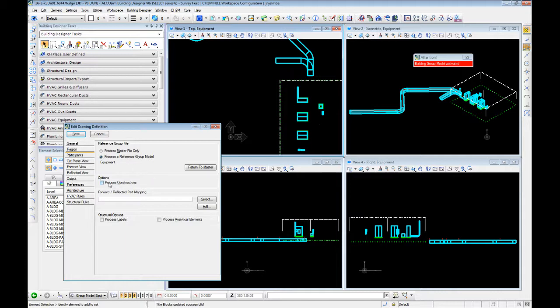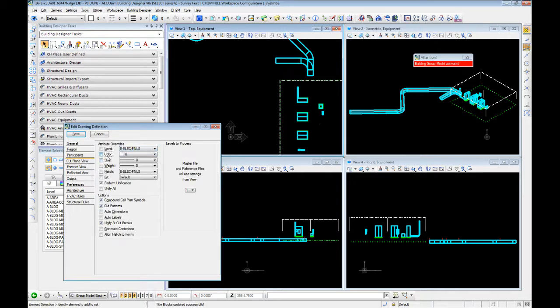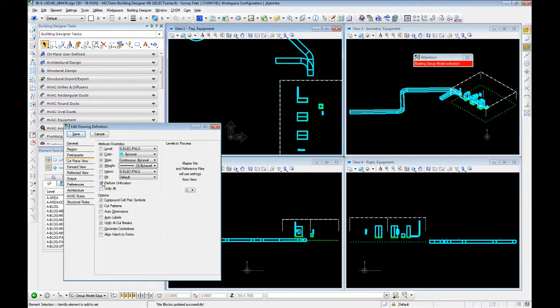When we get into some of our compound models and placing those in extraction, some require use of process constructions. If you're extracting and it doesn't look quite right, try checking that on. The structural options and forward and reflective part mapping we can ignore in electrical. Cut plane view and forward view we're going to set up very similarly — select color, style, and weight, setting these all to by level. Turn off perform unification because we want to see individual elements. Since our switchboards are back to back, if you left that checked you would only see one combined switchboard. We're going to use compound cell plan symbols, and we're going to turn off cut patterns and unify and cut breaks.